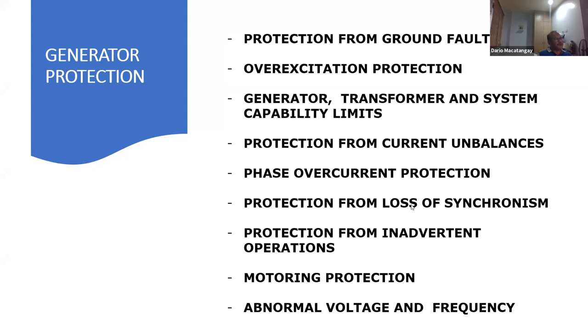Abnormal voltage and frequency, of course, we have that situation, and it needs to protect the generator because of that. There are some requirements in the grid. We have the grid code here in the Philippines that requires us to maintain some frequency during operations to maintain the system. But then, of course, voltage can be dangerous. It can go to a high value. Let's say you get a high volts per hertz, and that can be an overexcitation issue. Then you can actually damage the generator. Okay, so let's move on.